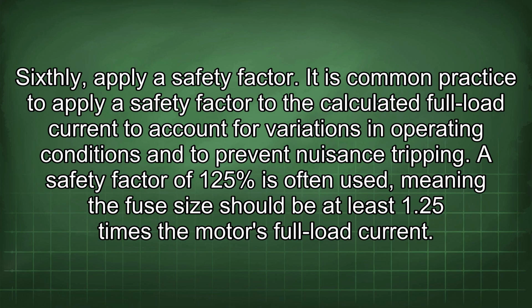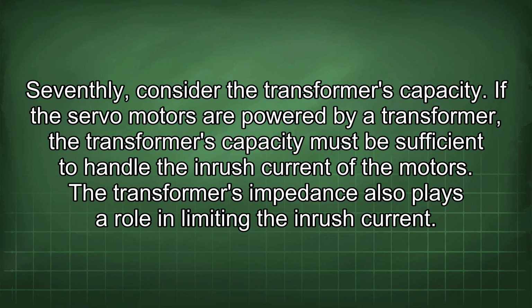full load current. Seventhly, consider the transformer's capacity. If the servo motors are powered by a transformer, the transformer's capacity must be sufficient to handle the inrush current of the motors. The transformer's impedance also plays a role in limiting the inrush current.